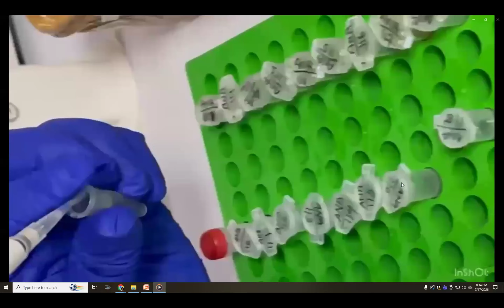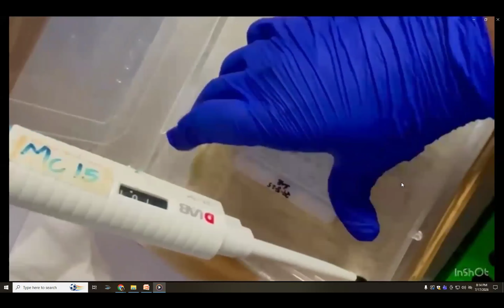Mix thoroughly using a vortex for about 4 seconds. The diluted sample should be used within the same working day. Sample loading is done by adding 30 microliter diluted sample to each reaction field, including positive and negative controls. First incubation is done by placing biochip slide onto reagent tray and incubated for 30 minutes at room temperature. First washing is done by rinsing it with PBS tween, followed by immersion in PBS tween for 5 minutes.